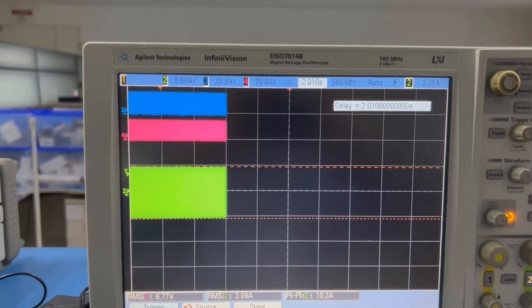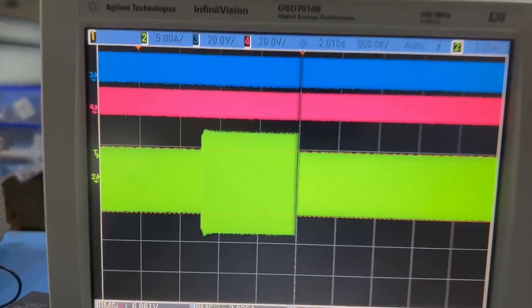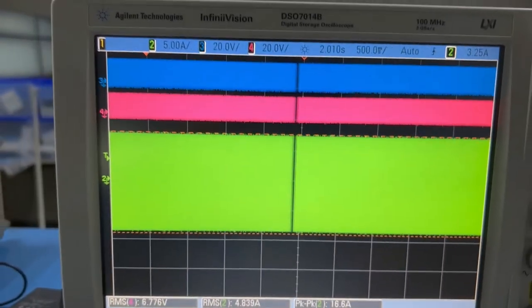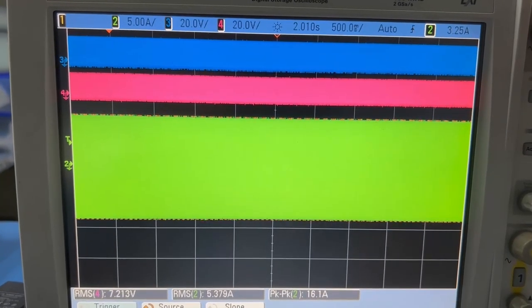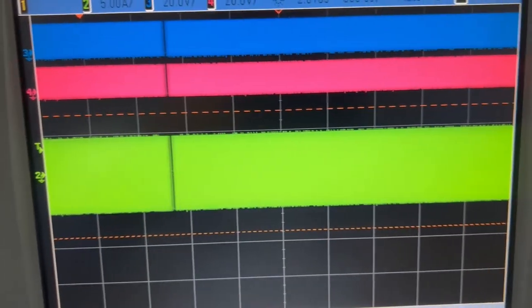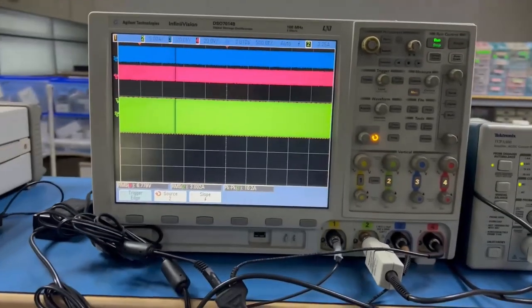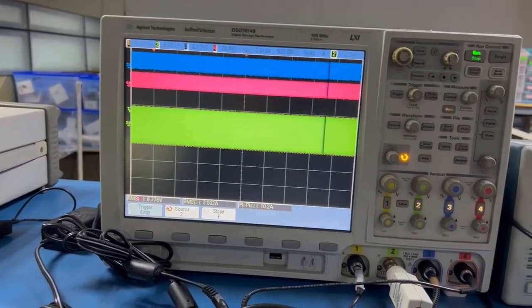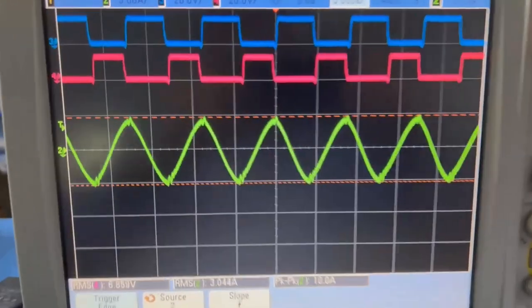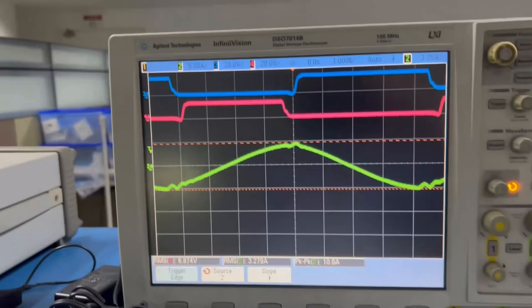We increase the current of this system to 25 amperes — doing a slow roll so you can see the actual transient response. You can see the load has been stepped from 5 to 25 amperes. There was absolutely no overshoot. Then cycling the load from 25 amperes down to 5 amperes again, it recovered very quickly. Because this is a battery charger application we don't need a very fast transient response — we have a moderately fast loop — but there is absolutely no overshoot or undershoot in the resonant current waveform.